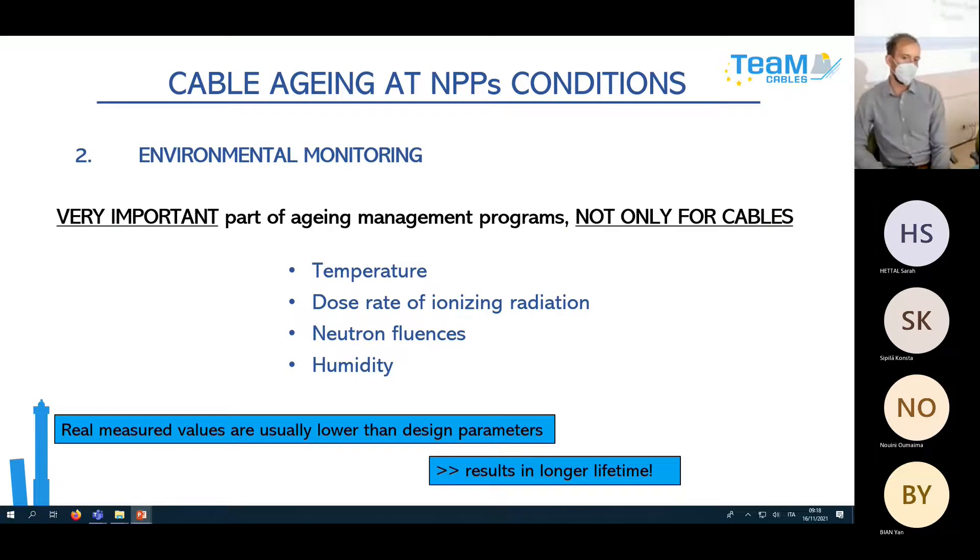Environmental monitoring is a very important part of the aging management program — not only for cables but for all equipment. Through this we get data about temperature, dose rate of ionizing radiation, neutron fluences, and humidity. If a cable goes through 10 rooms, you have to choose the worst — most harsh — conditions for prediction.